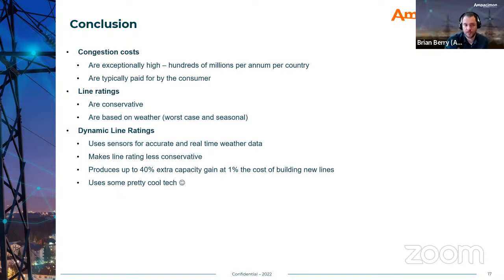Dynamic line ratings help. Traditional line ratings are conservative - they're always based on weather, because it's about how much cooling you're getting from the weather conditions. But which weather do you use? The worst case weather, or real-time weather? Weather from a weather station, or from a sensor directly mounted on the line? Dynamic line rating uses sensors directly mounted on the line - they're accurate, they use real-time weather. It makes the line rating far less conservative, takes away the guesswork, and produces up to 40% extra capacity gain at around 1% of the cost of building new lines. So 1% is nothing compared to the cost of those new lines.